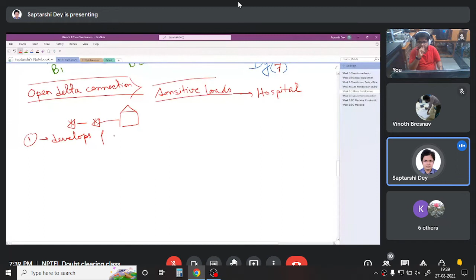So what is done in open delta connection? You have, say, a delta transformer supplying a hospital building. You can imagine it as three single phase transformers. Out of them, one transformer develops a fault. In such a case, you cannot completely turn off the transformer, turn off the supply, and then do repairs. At least for some time, you have to keep the supply on for the emergency loads, say the incubators or other life-saving loads. For such cases, this open delta connection becomes important.